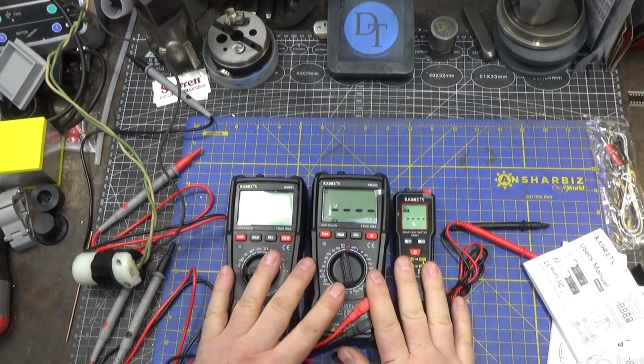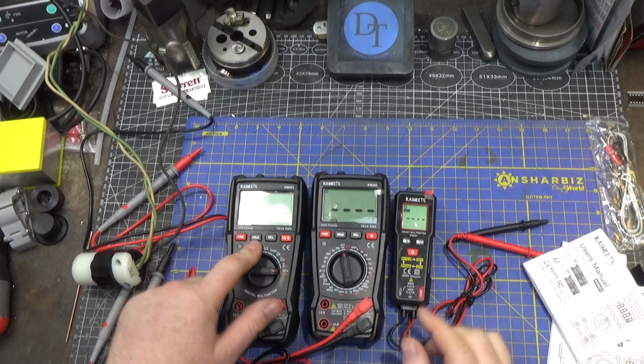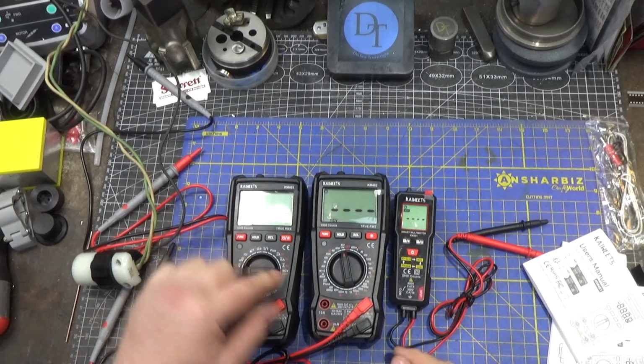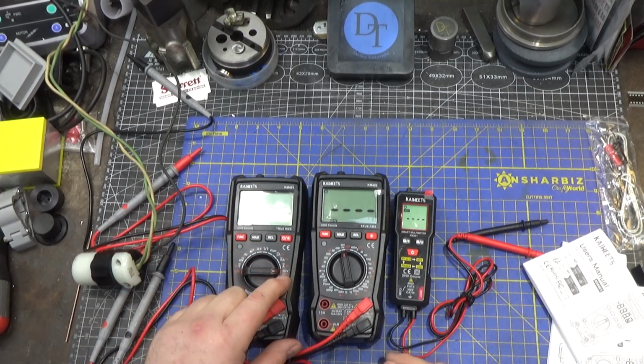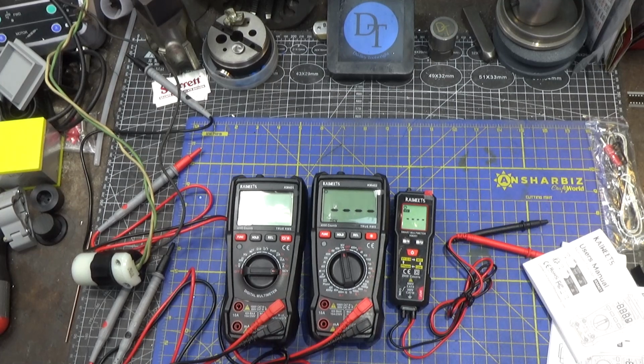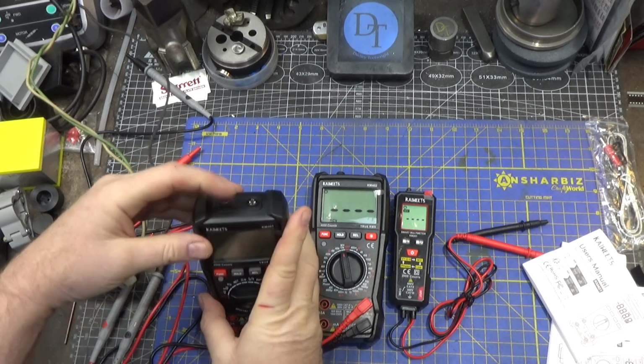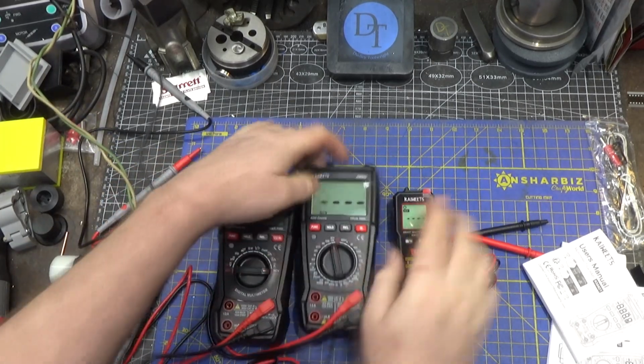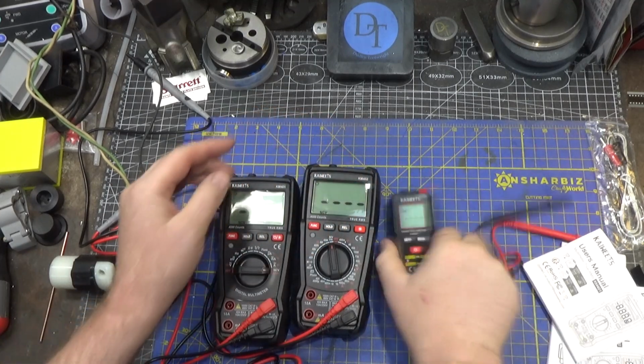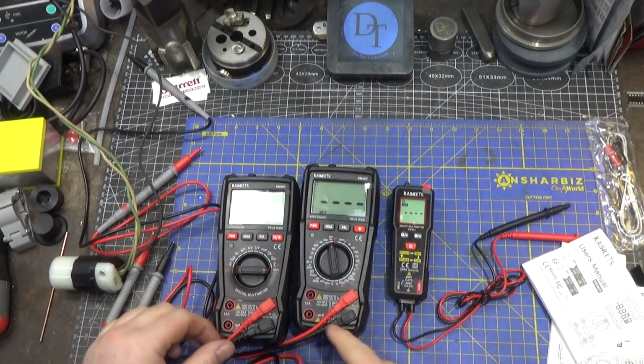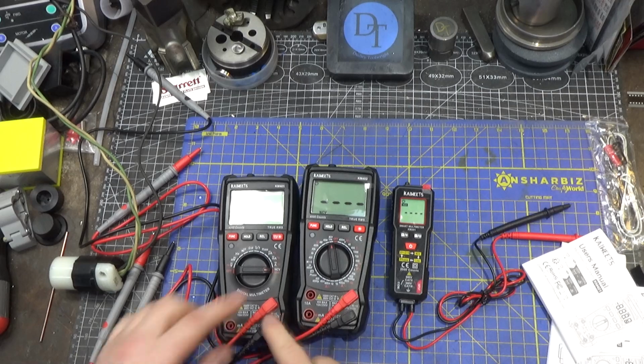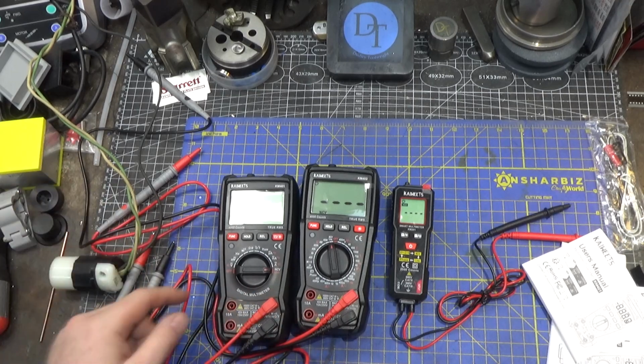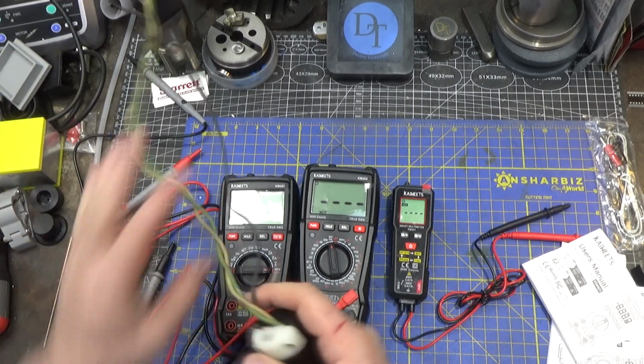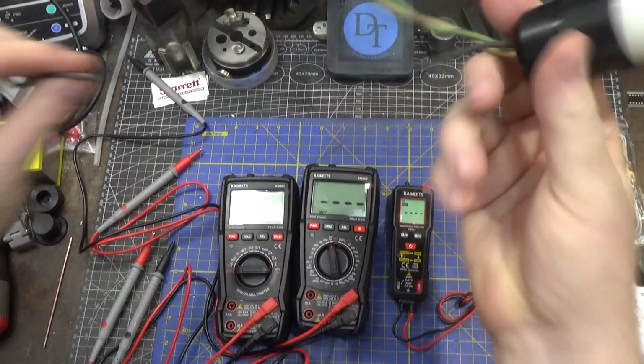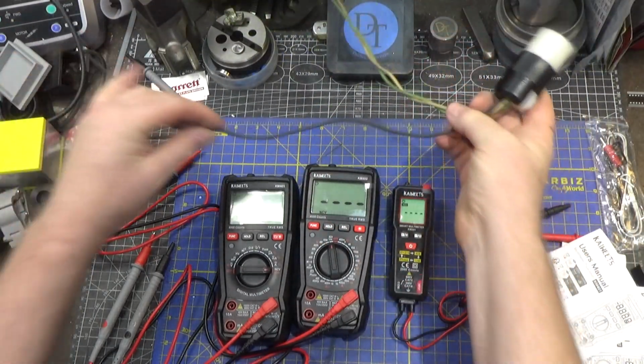Last time I looked at this meter, the 401, I noticed there was a non-contact voltage function and a live setting, and I didn't make the distinction between the two. The non-contact voltage section uses the sensor on the end. All three of these have that. The live function uses just the plus probe, like it does in phase mode, to detect if there's a live circuit. So this is plugged into the AC outlet, and this is the hot.